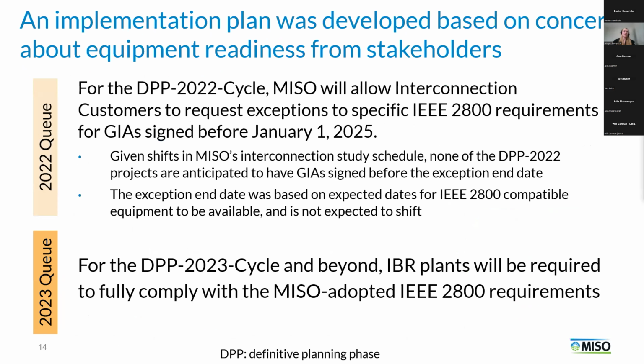Okay, and then additional stakeholder feedback we received was around our implementation timeline. Initially, we proposed to apply these requirements to IBR plants coming out of the 2022 interconnection queue without exceptions. We did get some feedback from stakeholders that some sort of flexibility was preferred, and it varied by OEM, but there were some requirements for clause 7 that current technology could not meet. They were still evaluating it. They had work underway to make sure that new inverters could meet the requirements as well.